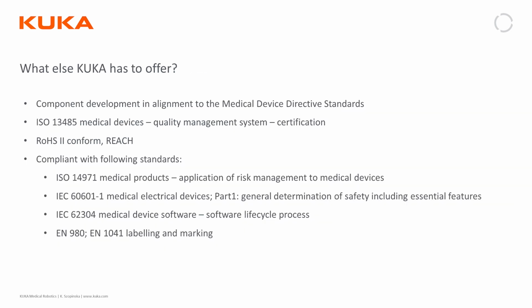What KUKA also offers is confirmation that we apply the ISO 13485 quality management norm for medical devices; we are regularly certified according to this norm. We also provide RoHS and REACH certificates, as well as comply with further medical standards as far as applicable. For example, the 14971 norm for the application of risk management to medical devices, we fulfill as far as we can, as the LBR Med does not have a final defined medical application, so we cannot evaluate the whole future medical device. We also apply the norm for the medical software lifecycle process, as well as norms for the labeling and marking of the robot.